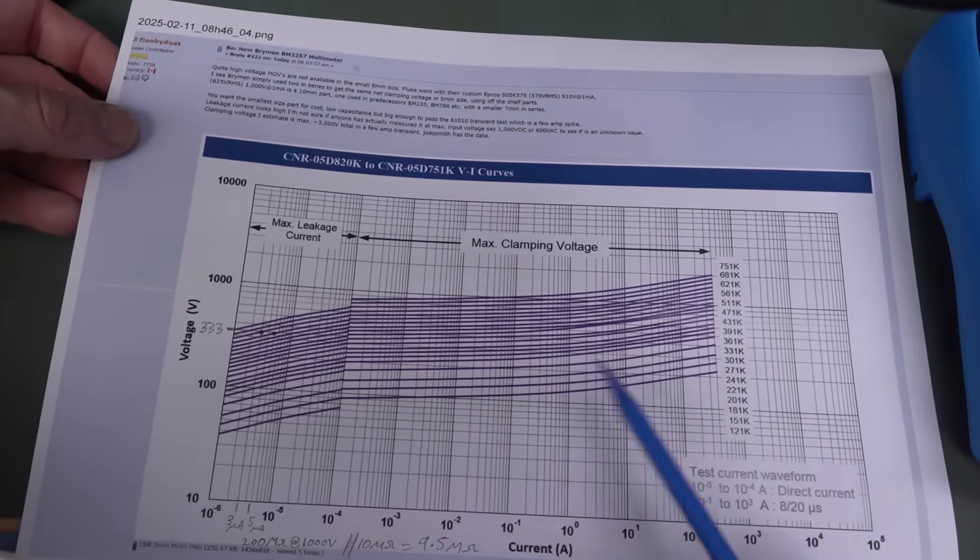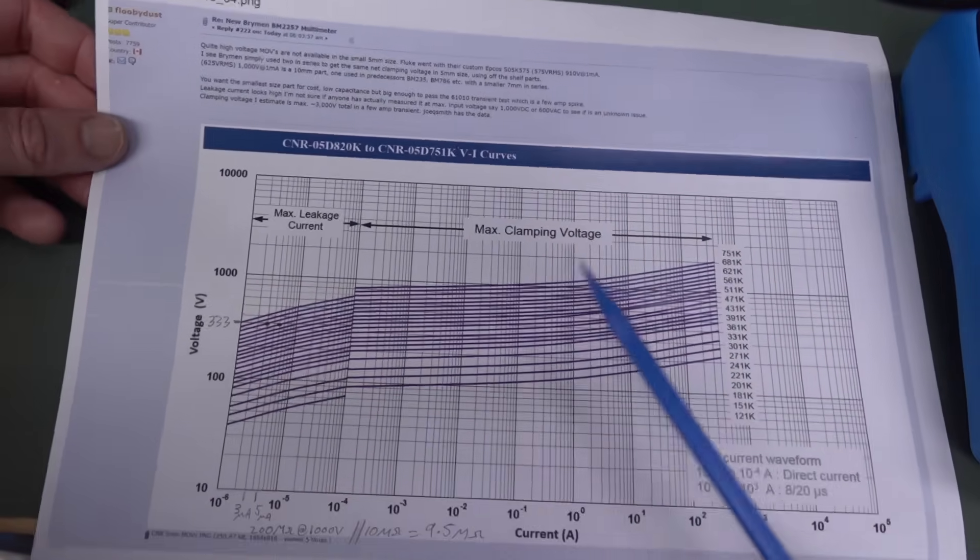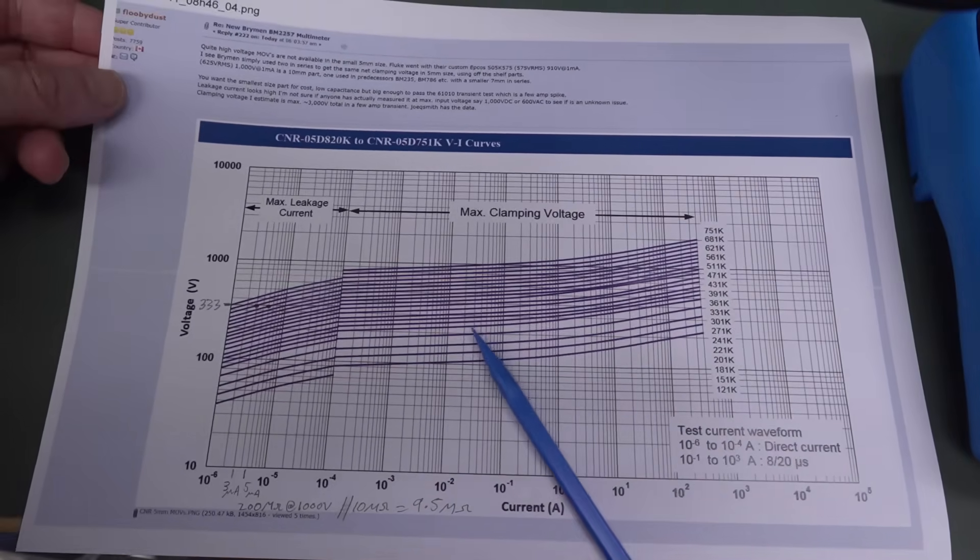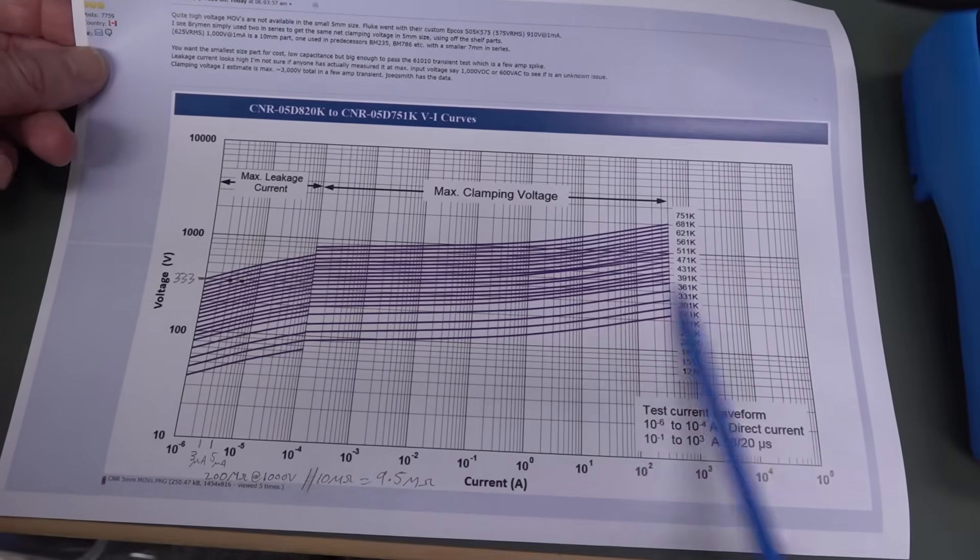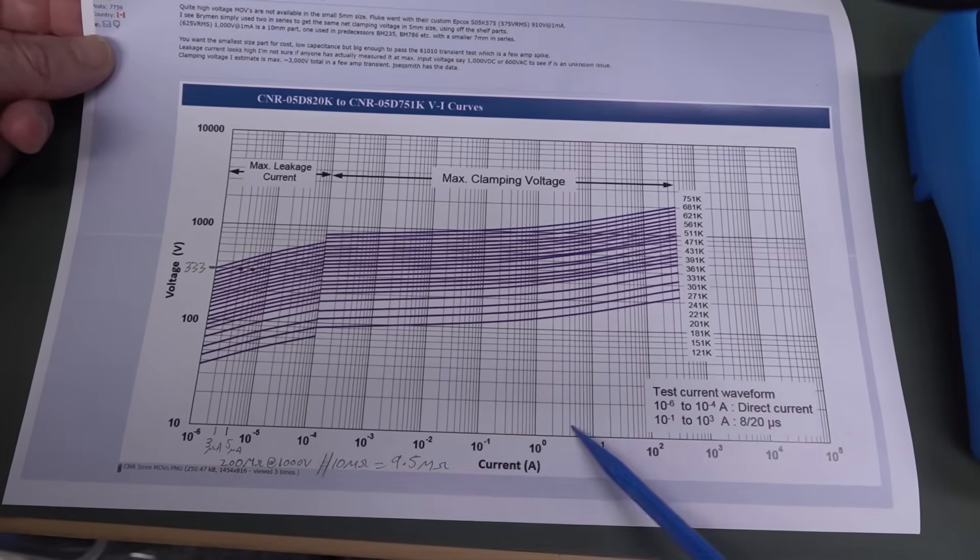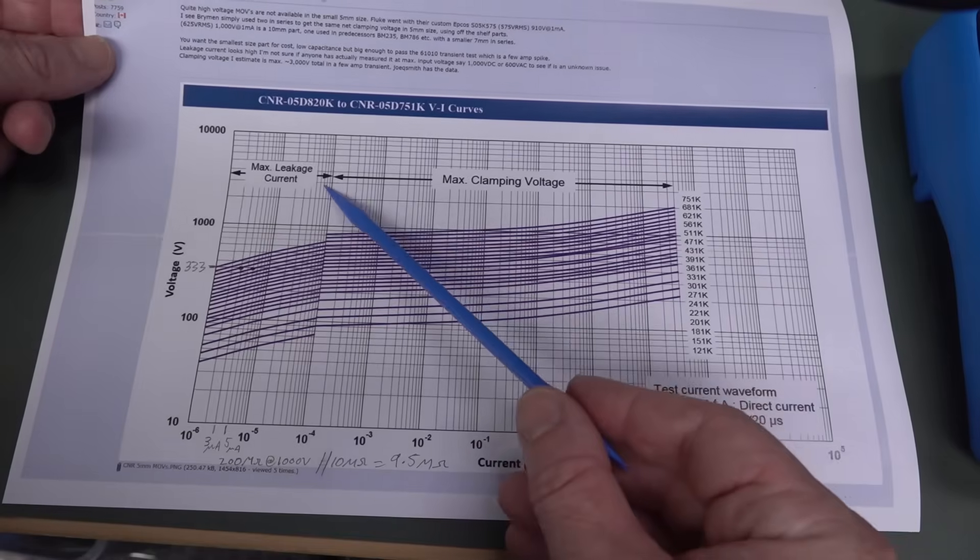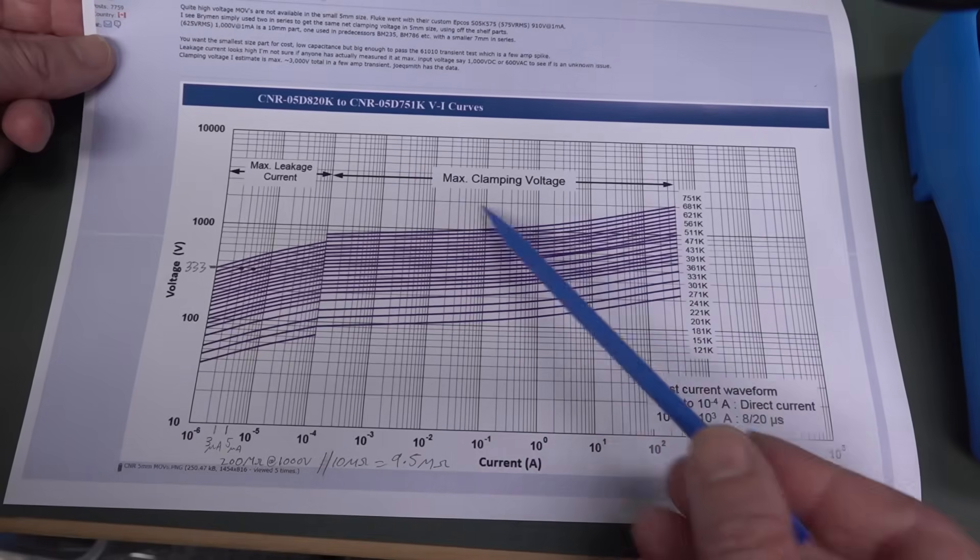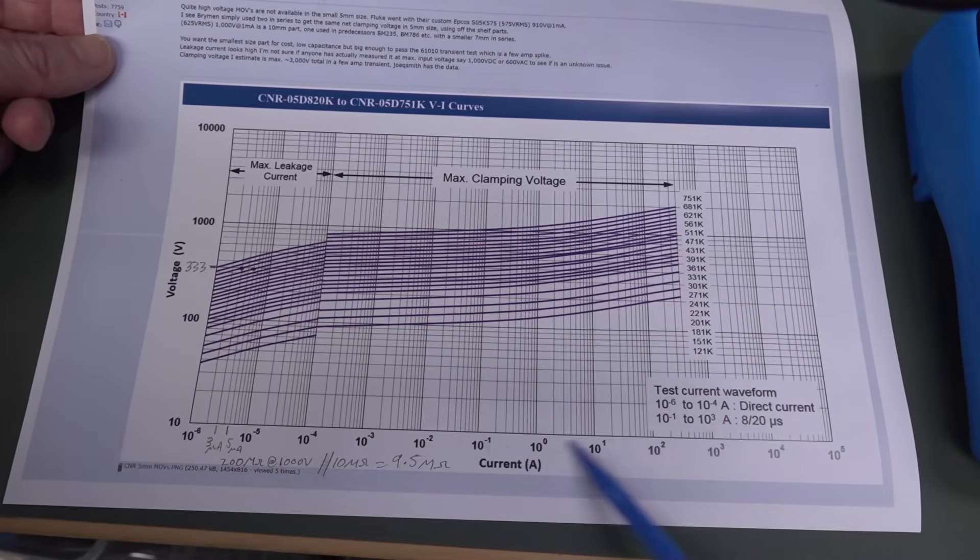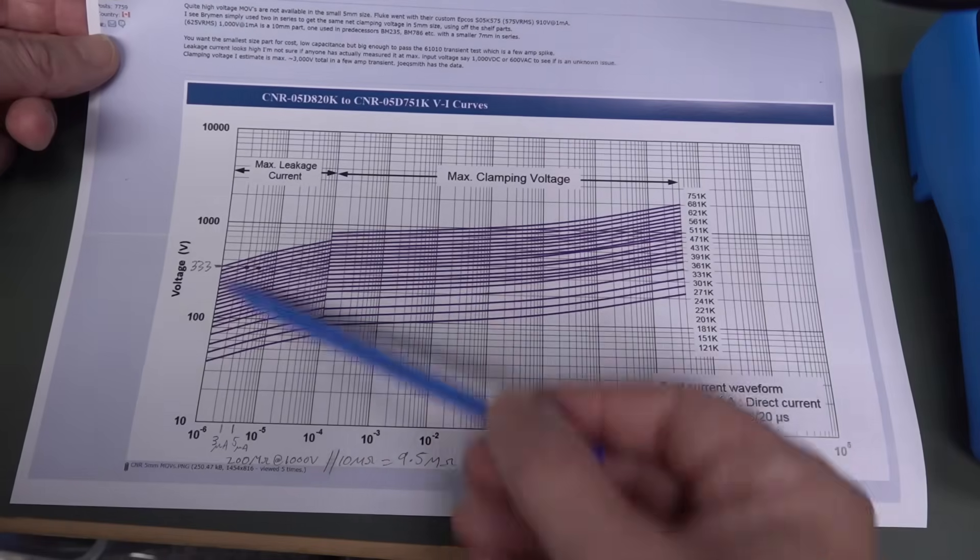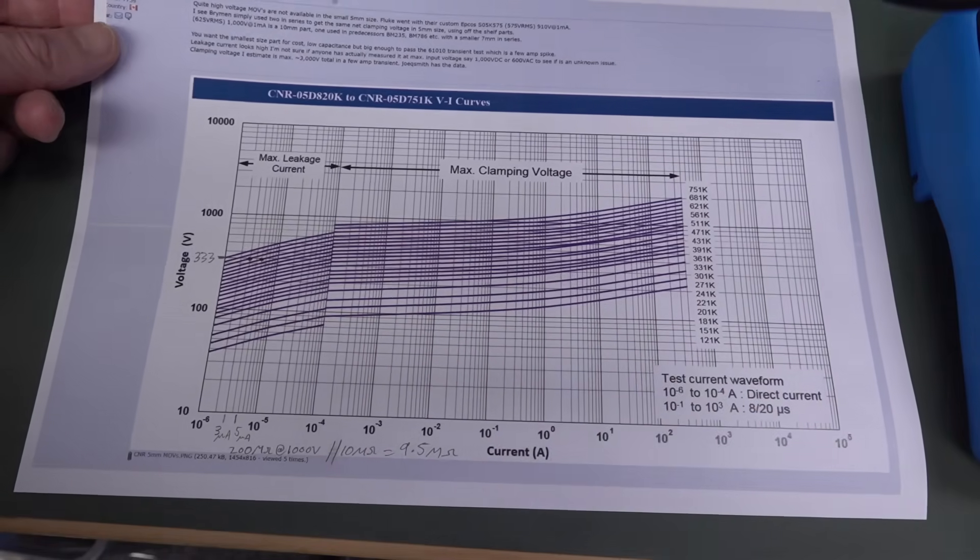So you can actually get this entirely from the data sheet, and this is the post by Flubby Dust. I'll link the data sheet down below for these CNR brand MOVs. It has these characteristic curves in here, which is basically voltage versus current down here. And this is, they've split it down here. You can see this is when it's at max clamping voltage.